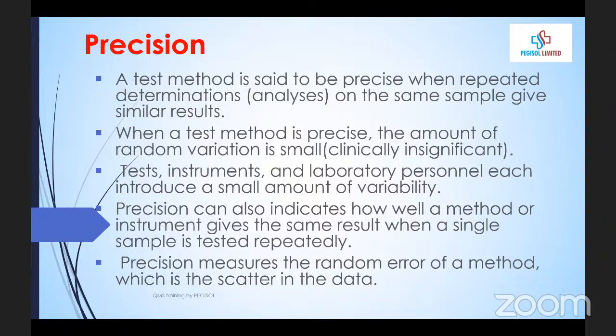In other words, it's clinically insignificant. So 4.1 millimole per liter to 4.2 millimole per liter, that's a clinically insignificant difference. The test, the instrument, and the laboratory personnel each introduce a small amount of variability. So test method, instrument, and personnel have a way of introducing what? A small amount of variability. So precision can also indicate how well a method or an instrument gives the same result when a single sample is tested repeatedly. So you test a sample, you run it, now you run it again, run it again, run it again. You want to see if that equipment can give similar results.